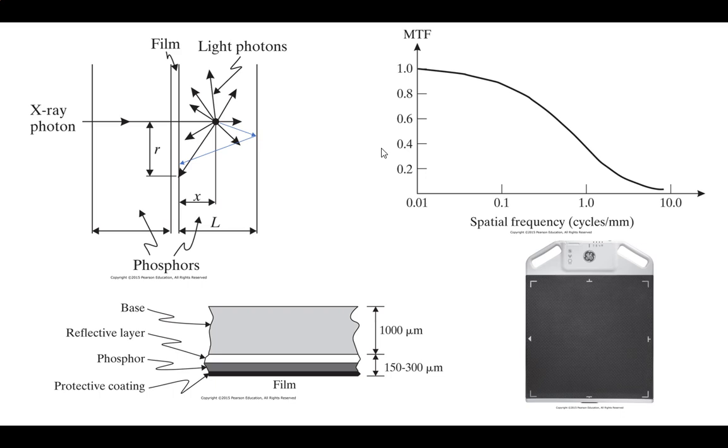This, you can see the material, this is just the structure to keep it rigid. Inside this on both sides, it's got this on both sides, that's just structure. It's got a thin reflective layer, usually titanium dioxide or something of that sort that'll reflect fairly nice. Then the phosphor layer, then a protective film, slide your film in, boom, slap it shut. You'll get exposure from both directions from the phosphor.